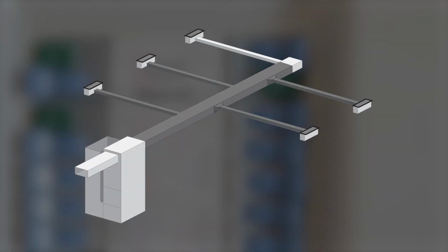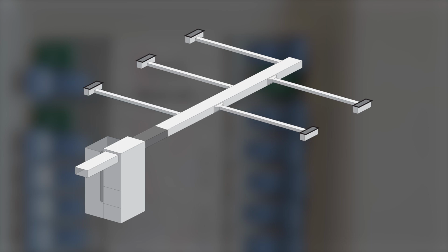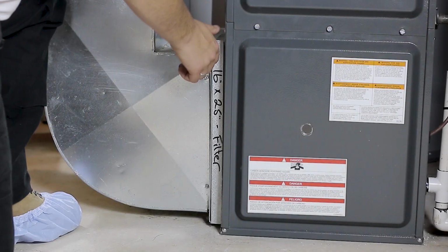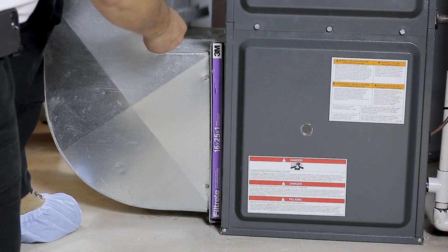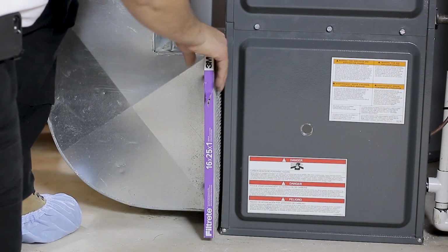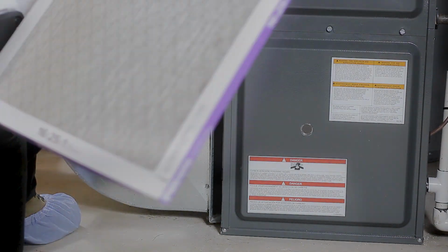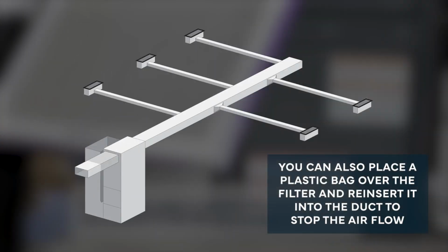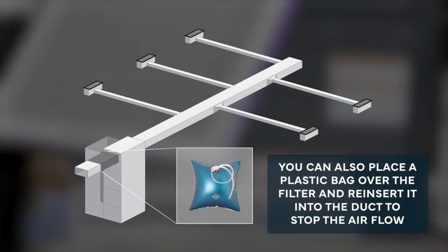When cleaning an air conveyance system, the supply and return duct networks are cleaned separately. This is done to avoid pulling debris through the heat exchanger and coil. The supply and return can generally be separated by pulling out the furnace filter and inserting an inflatable zone bag into the air handler to isolate the supply from the return to block airflow.